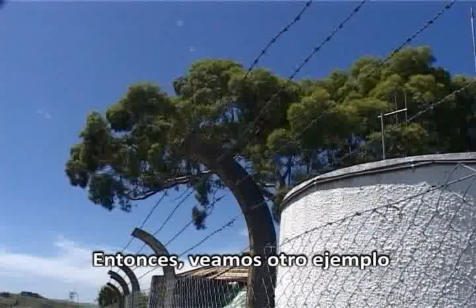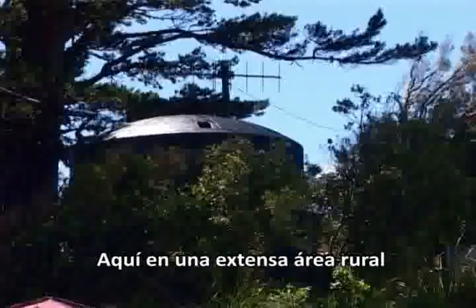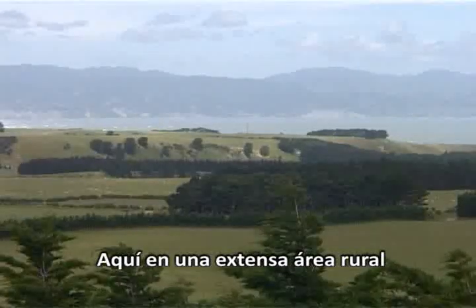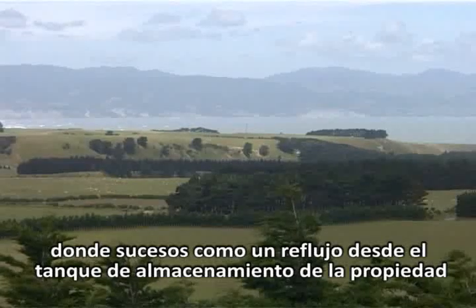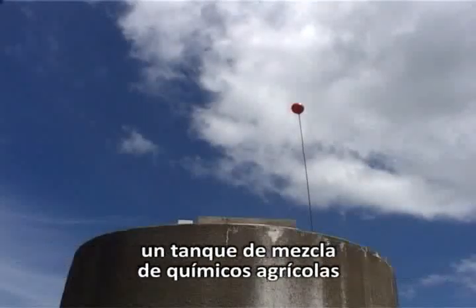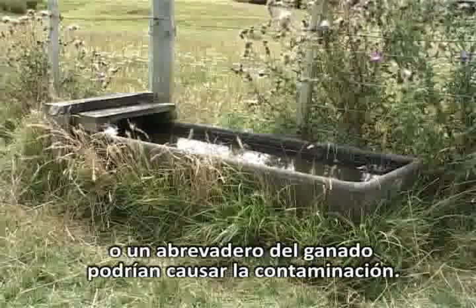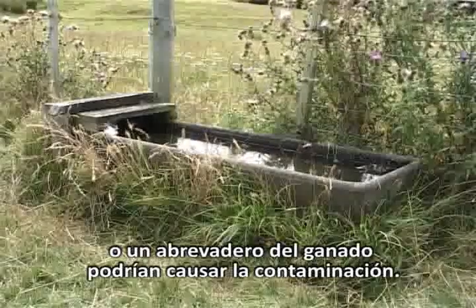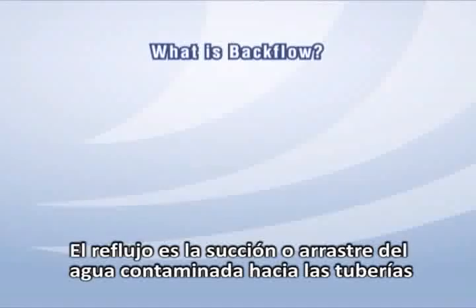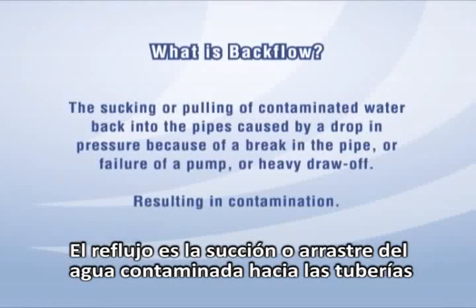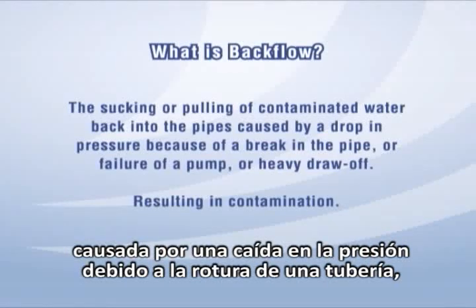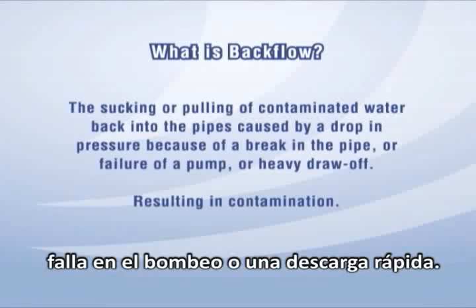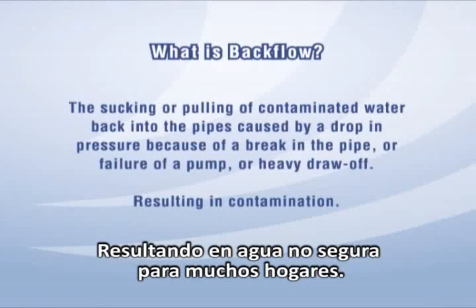So let's have a look at another example. Here in a very long distribution through a rural area, events such as a backflow from a property storage tank, farm chemical mixing tank or a stock trough could cause contamination. Backflow is the sucking or pulling of contaminated water back into the pipes caused by a drop in pressure because of something like a break in the pipe or failure of a pump or heavy draw-off.